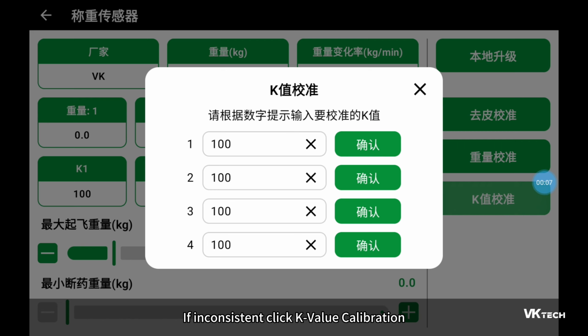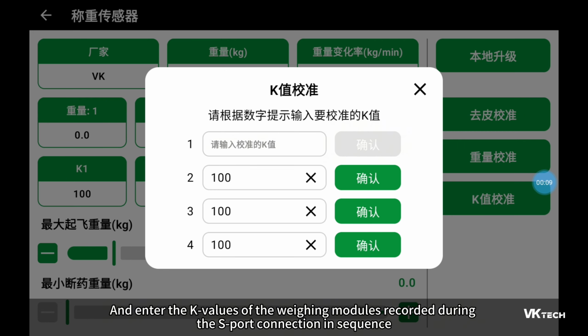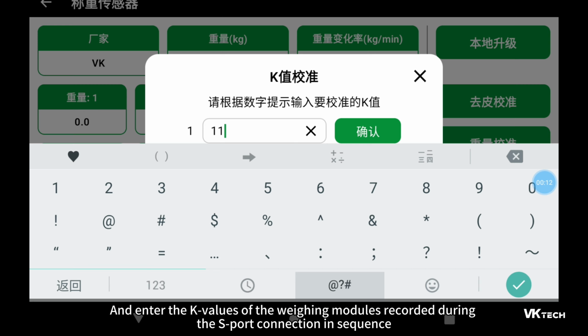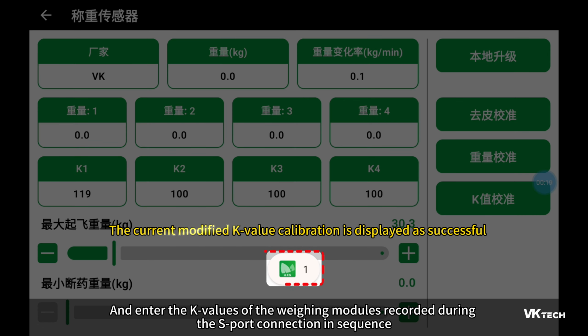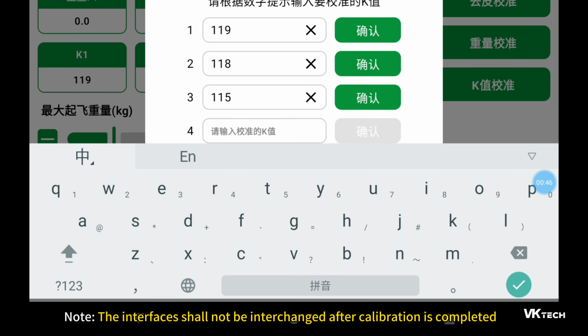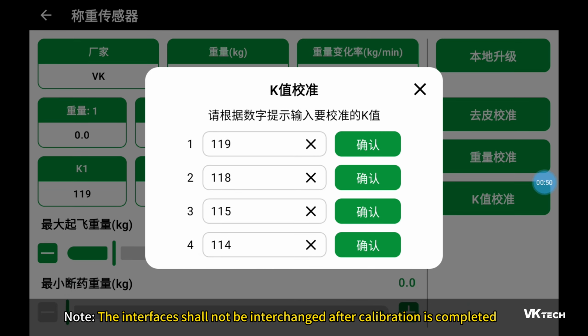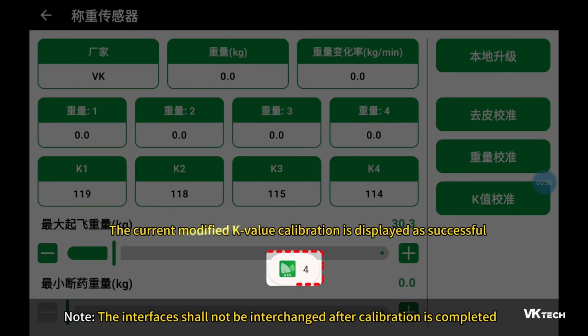If inconsistent, click K value calibration and enter the K values of the weighing modules recorded during the S port connection, in sequence. Note: the interfaces shall not be interchanged after calibration is completed.